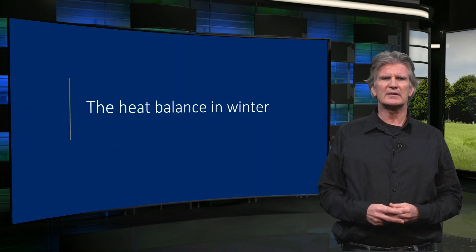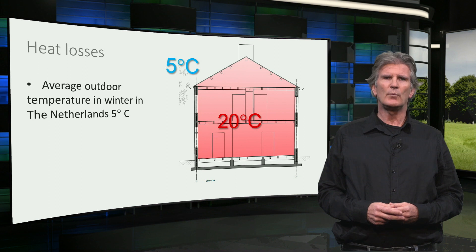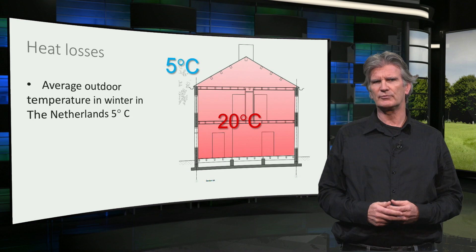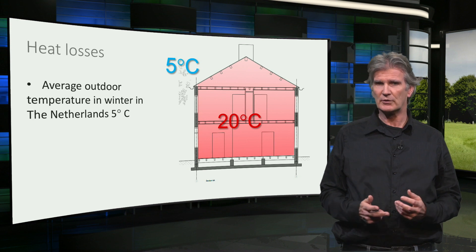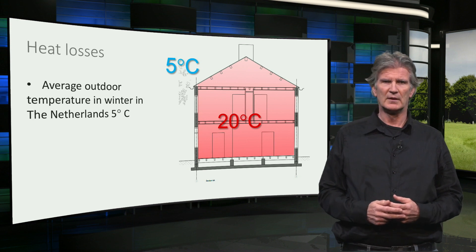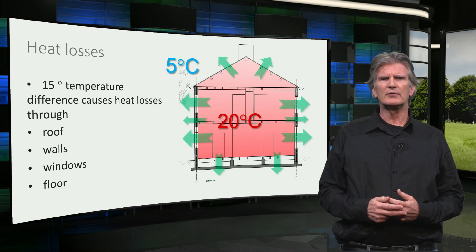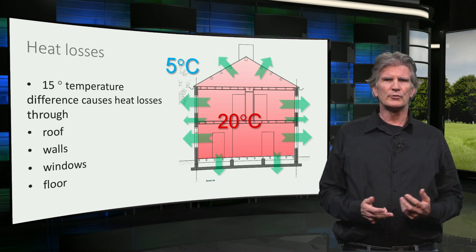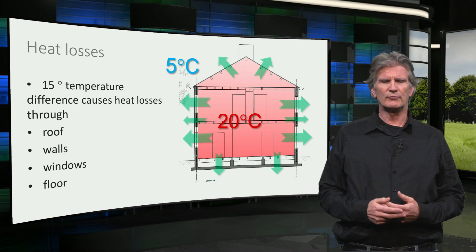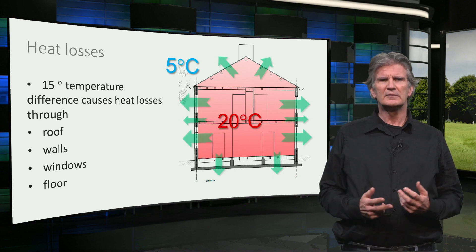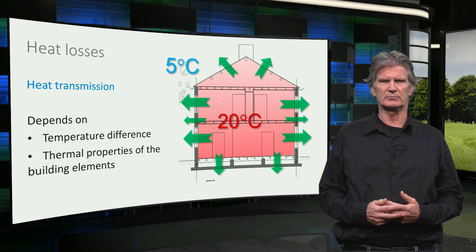First, let's have a look at the heat balance on a winter's day. In winter the house is heated to around 20 degrees centigrade, where the average outdoor temperature is, for example, 5 degrees in the Netherlands. This 15 degree temperature difference causes heat to flow through the building envelope — the roof, the walls, the windows, and the floor. This is what we call heat transmission.